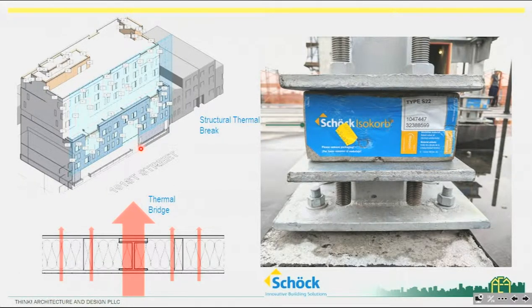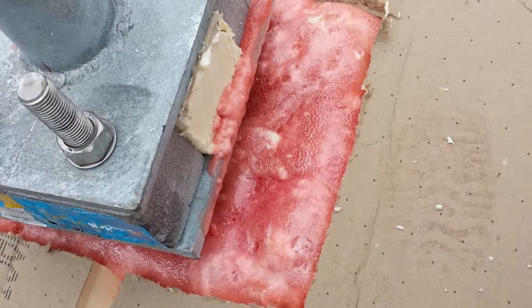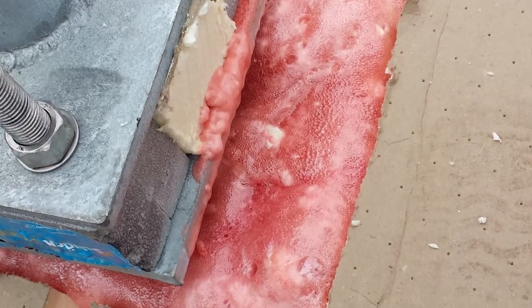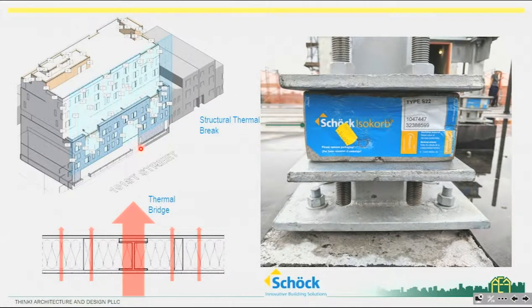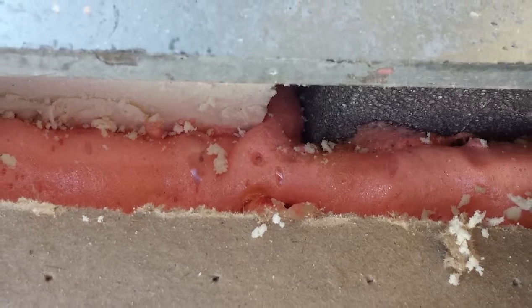Insulation outboard of the studs is one example. Up on our roof, we have two rooftop HRVs providing ventilation to the building, but that structural steel dunnage needs to connect back down to the concrete. To break the thermal bridge between the concrete deck and the steel dunnage, we use this Schöck product — a structural insulation product with stainless steel bolts that breaks the linkage between the steel dunnage and the concrete.